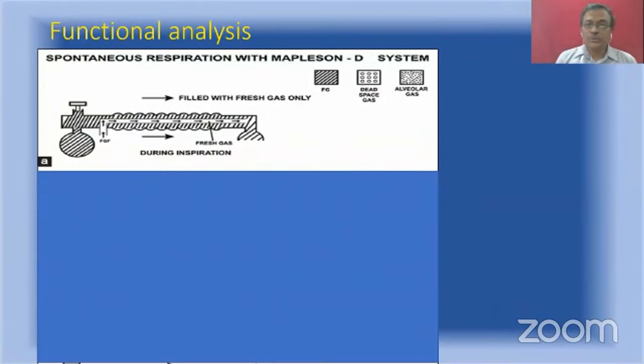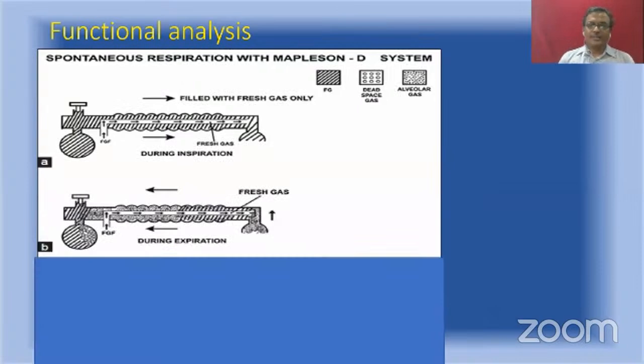Now, let us go on to the function analysis. What happens when the Bain is used for spontaneous respiration? The initial picture during inspiration, see the whole system is filled with fresh gas flow. There is no confusion. So the fresh gas will go to the patient and the bag will collapse. The next phase, the expiration is happening. You can see the alveolar gas, which is following the dead space gas, is entering the outer tube. You can see the outer tube. And it is moving towards the reservoir bag. And its movement is facilitated by the fresh gas flow coming through the inner tube. I said, it never stops. It continues, whether it is in inspiration or expiration or expiratory pause, it continues to flow.